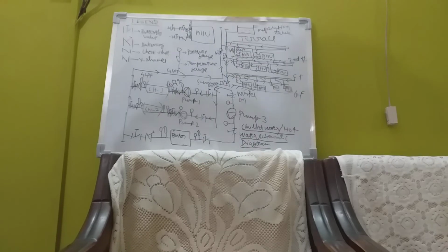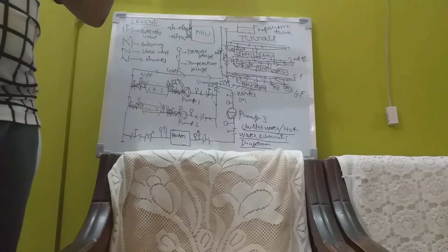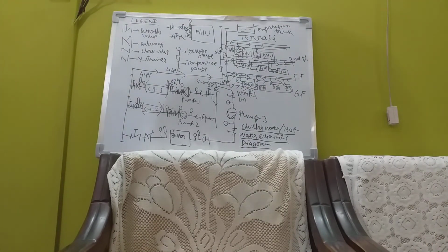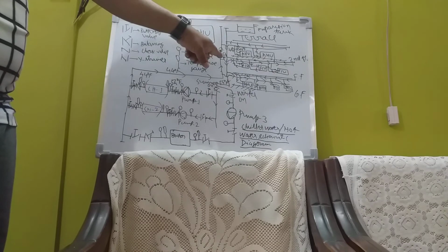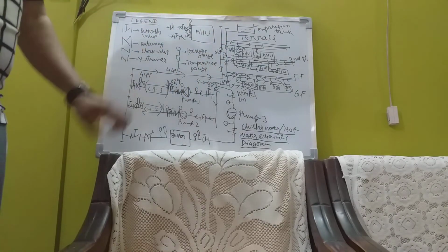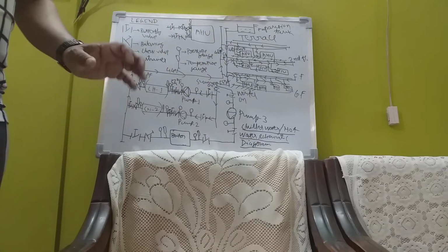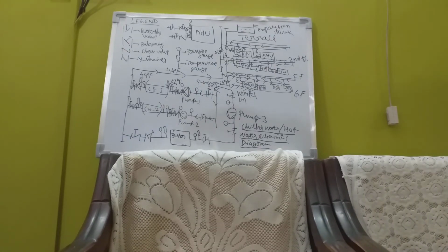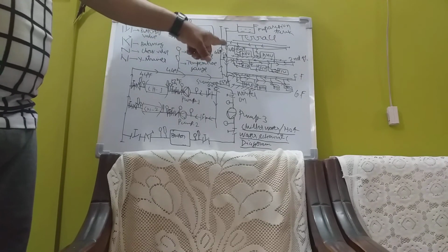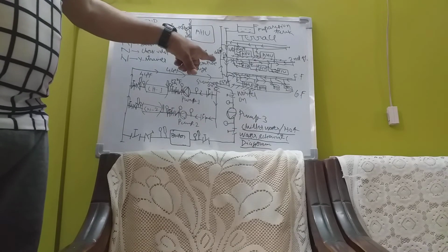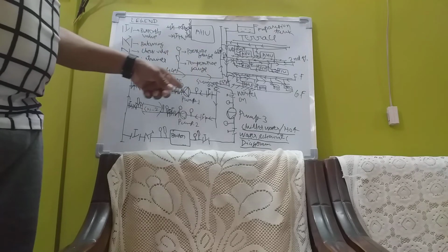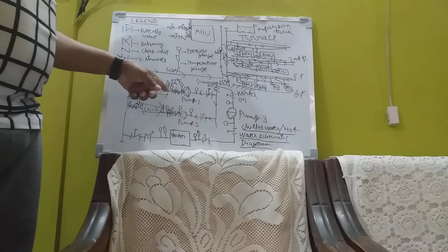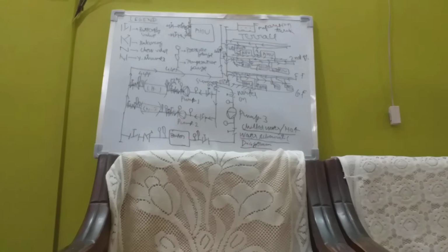You should understand that maintaining this temperature delta T of 10 degree Fahrenheit is very, very important. If instead of 54 degree it becomes 53 degree Fahrenheit, the temperature system will collapse. That we cannot do. That's why the water going out from the AHUs and going to the chilling machine must be at 54 degree Fahrenheit, and it comes out at 44 degree Fahrenheit.